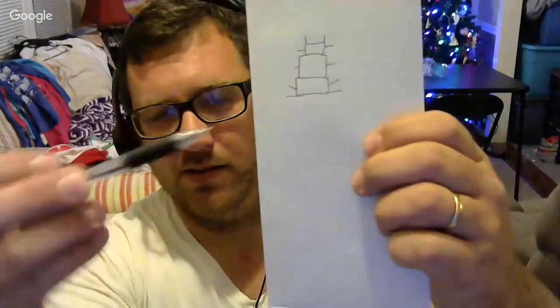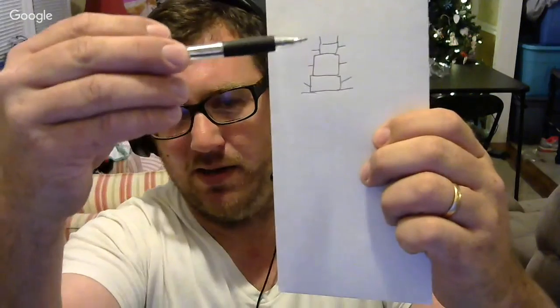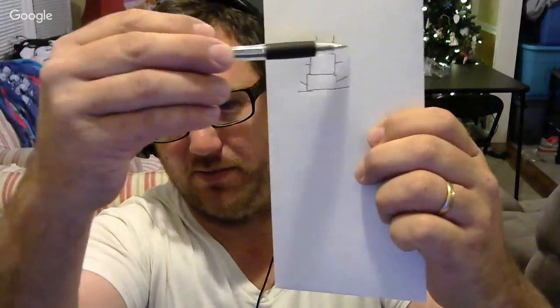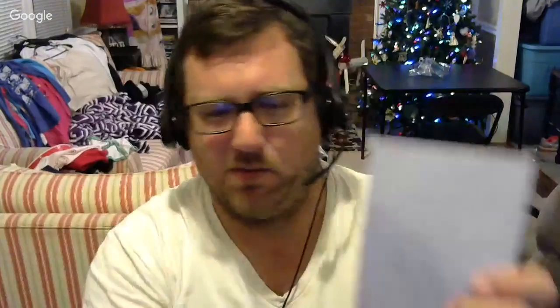Here's a sequencer: you'll have the low voltage on either side of the bottom, a set of high voltage terminals there, and another set of high voltage terminals up top. There'll be like 5kW running through here and 5kW running through there. The low voltage signal — the W wire and common — will be at the bottom. One side is the W wire, one side is common, then you have two elements on a double stack. A single stack is basically the same except it's taken off the top, connected internally.